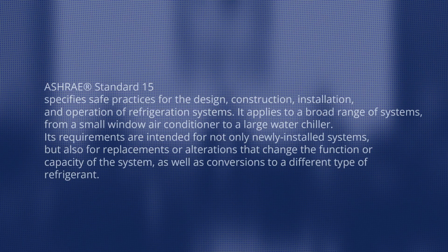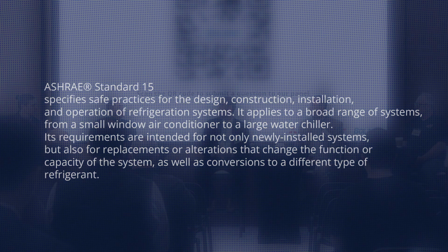And then you both mentioned ASHRAE 15, so refrigerant calcs. For those who don't know, we went through a recent phase out. We've switched from R410A with high pressure systems to either R32 or R454B. Those are both now A2L refrigerants. So I'd like you to share some of the impacts that's had on the design, going from our legacy refrigerant to the new refrigerant and why that may be a bigger impact on your ASHRAE 15 calcs moving forward.